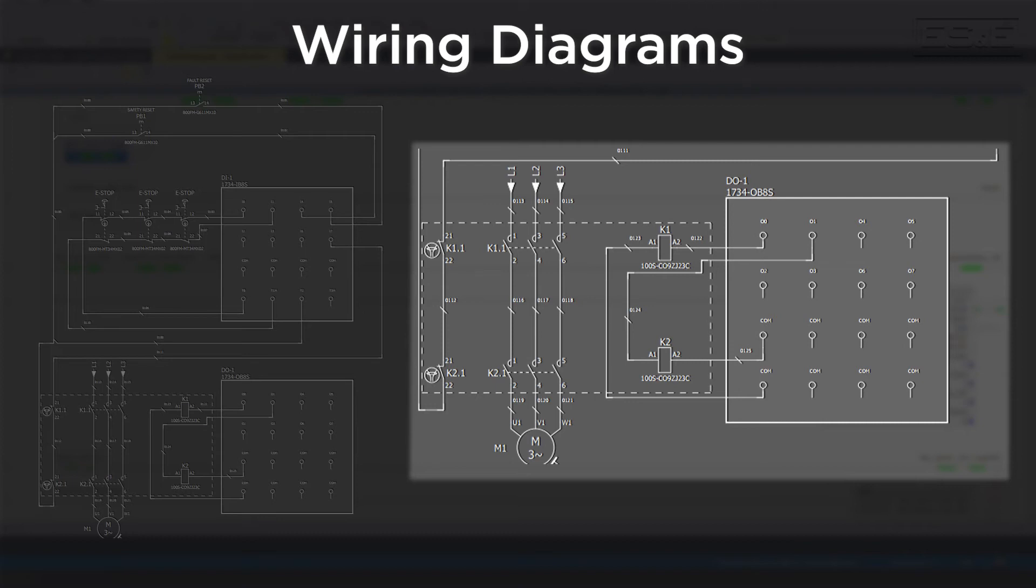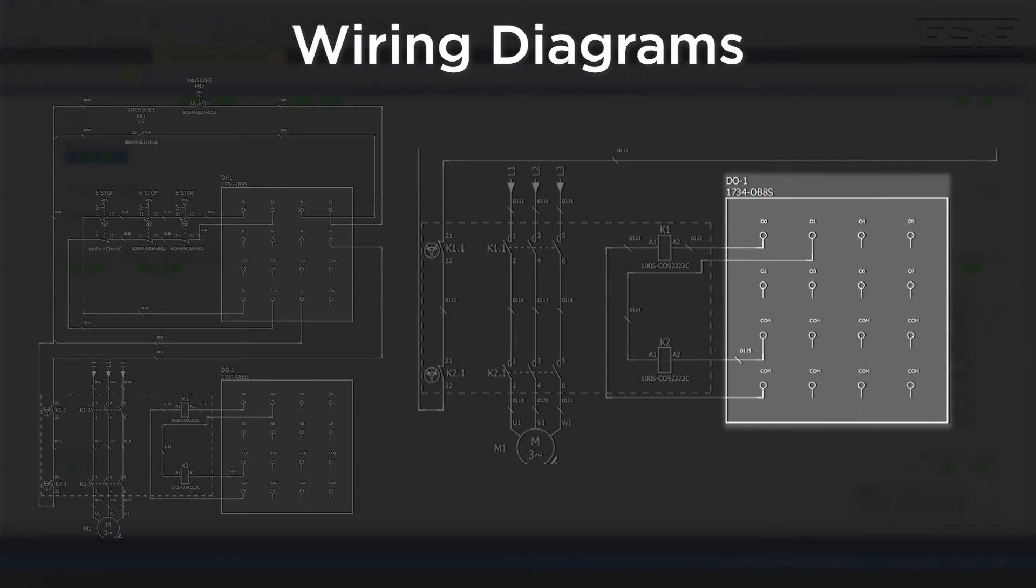This is a requirement for both performance level D and E systems. However, the feedback signal is not required to be a safety input, so you can drive 24 volt DC through the auxiliary contacts and feed that back to a standard input on the PLC system and map that into the safety task. Lastly, we need to wire the redundant relays to output 0 and output 1. Since we already have feedback wired, there is no special requirements for the outputs.